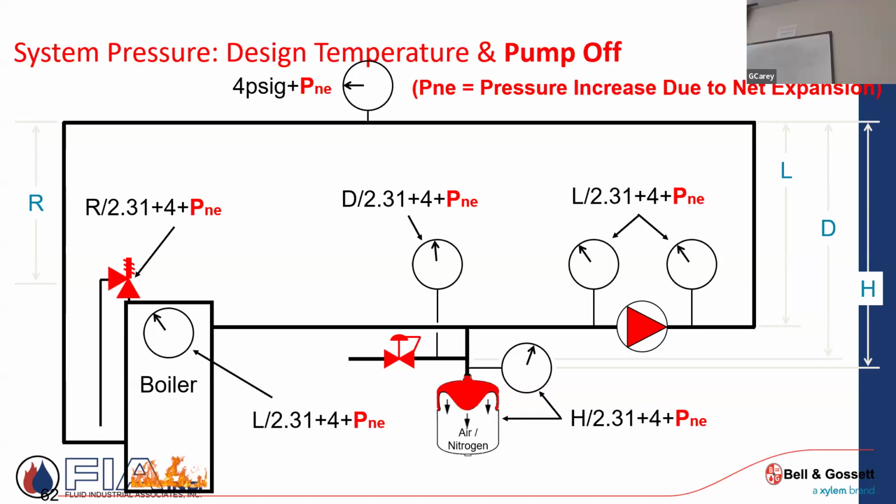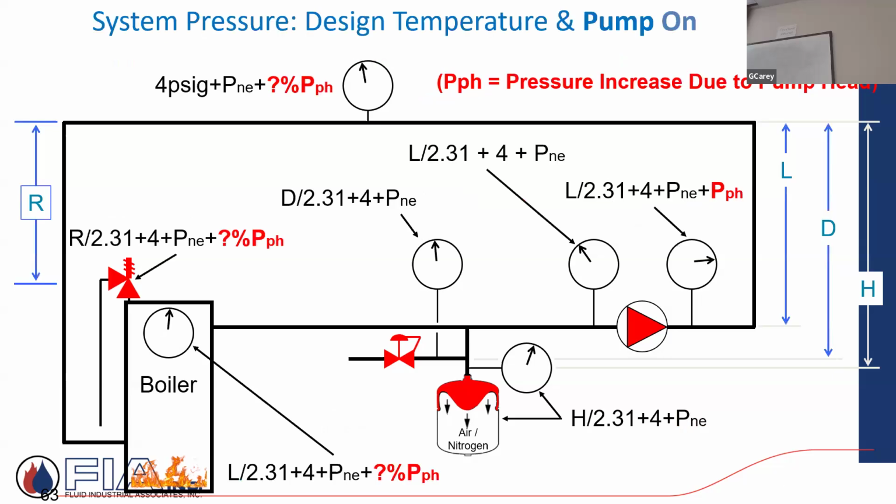And then if I fire the boiler and I have the pump off, I'm going to see this thermal expansion and I'm going to have water entering into the tank. And as long as it's sized and pre-charged properly, the pressure increase is going to happen, but it's not going to activate. It's not going to cause my relief valve to dump.